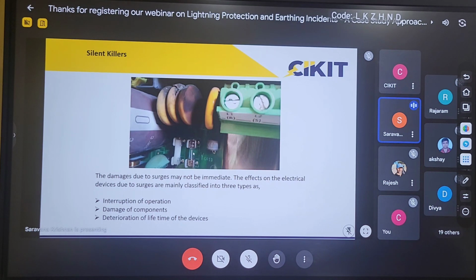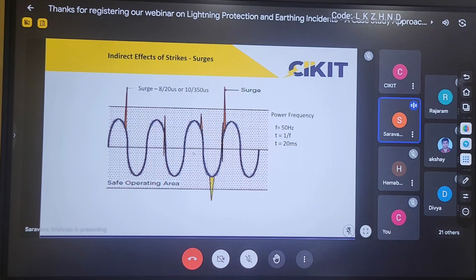For example, if I have equipment which is expected to have a lifetime of 5 years, and continuous surges of very low magnitude keep approaching over a period of time, then the lifetime of the equipment will be reduced from 5 years to 3 years. But the reason cannot be understood because the magnitude of the surges is very low. So these very low magnitude surges are always considered silent killers of electronic equipment. The surges we mentioned are very high magnitude but very short duration pulses, expressed as either 8 by 20 microseconds or 10 by 350 microseconds.